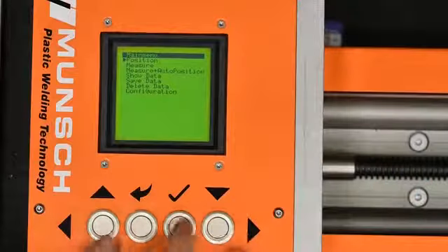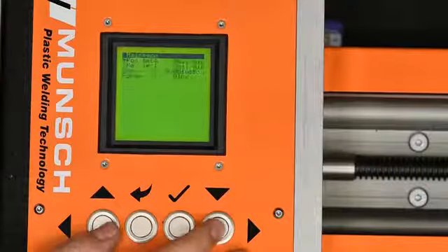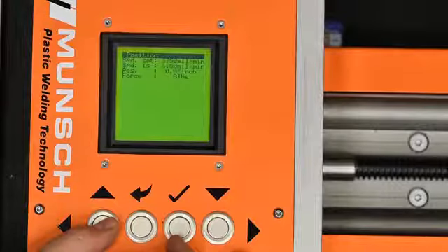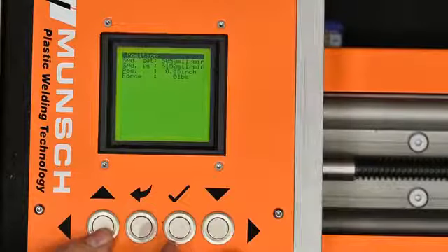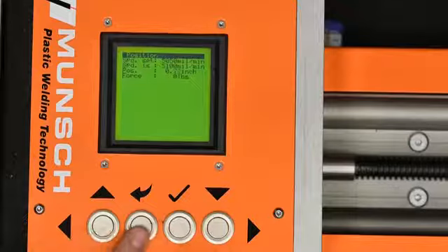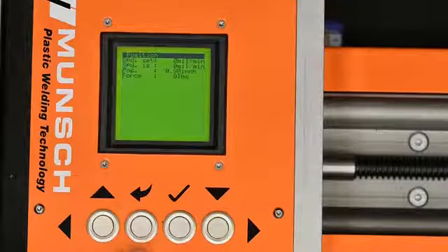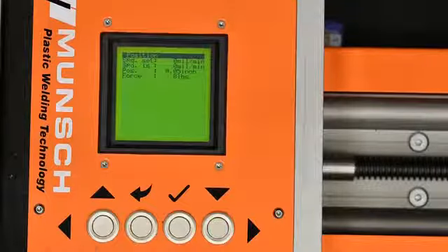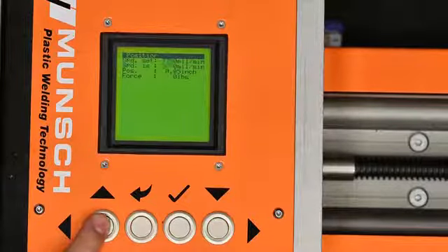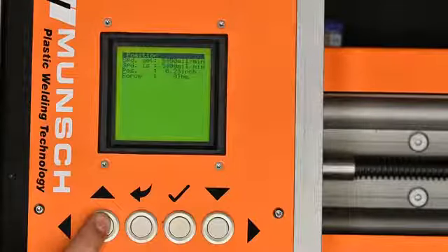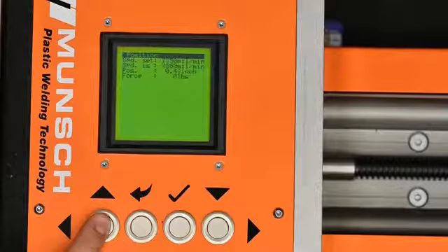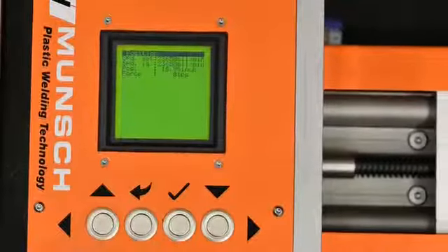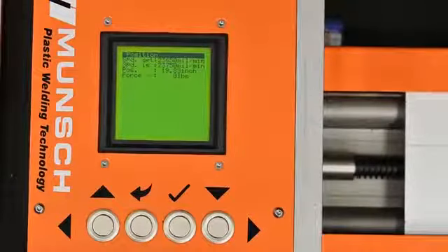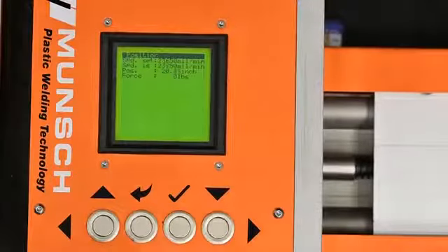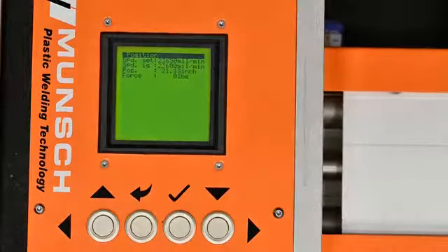You can move the slider if you select position in the main menu. You can stop the slider by pushing the return button. While it is moving, you can accelerate or decelerate by keeping the corresponding button pushed. The machine is protected against self-destruction by circuit breakers and automatically stops at the right and left end of the sliding area.